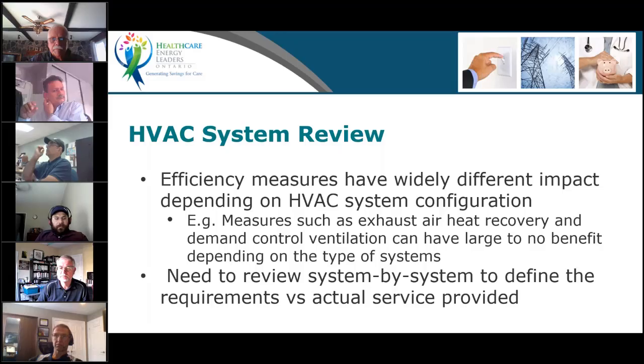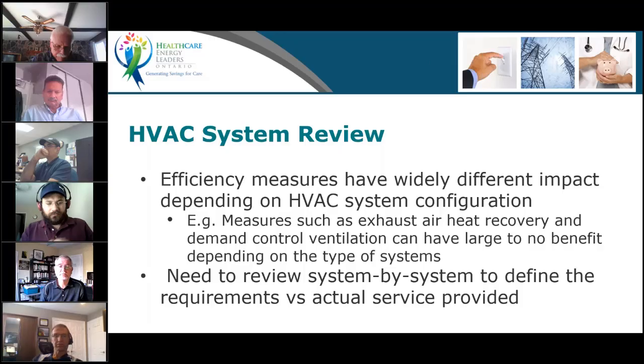But in order to look at that properly, you need to make sure you understand your HVAC system. Don't purely and solely rely on your contractors or your engineers. I've seen engineers install heat wheels and demand control ventilation on systems that should never have those. They were not suited for that, but they use this blanket recipe of putting heat recovery everywhere. On a 10%, 15% outside air VAV system, there is no need to have heat recovery in most places in our climate. So you have to be very careful. Make sure you, or your team, understand the systems, so that if somebody comes to you with measures for the HVAC system, you're well equipped to judge if it's a valid measure or not.